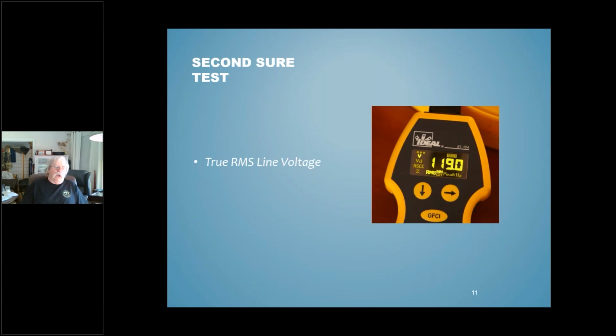The tolerance based on ABYC standards is plus or minus 10% of the nominal rating. And it will vary throughout the day depending on how much of a load there is on the grid in proximity to where you're testing.